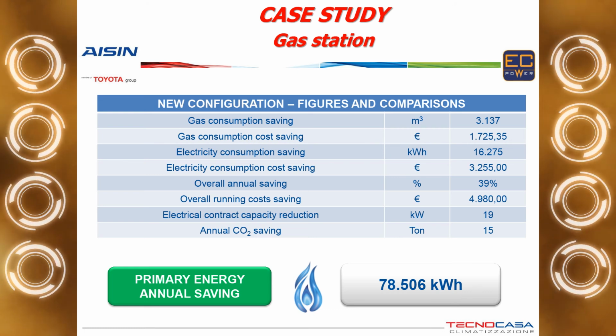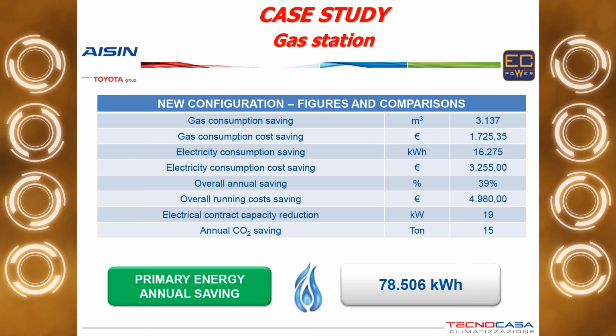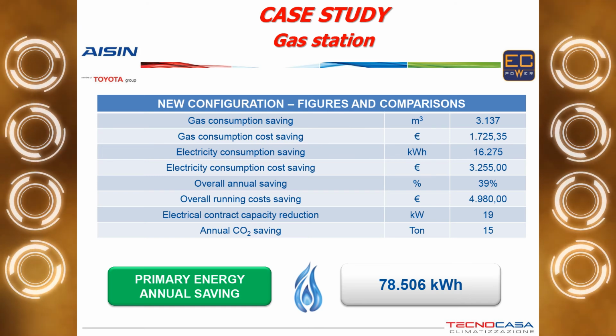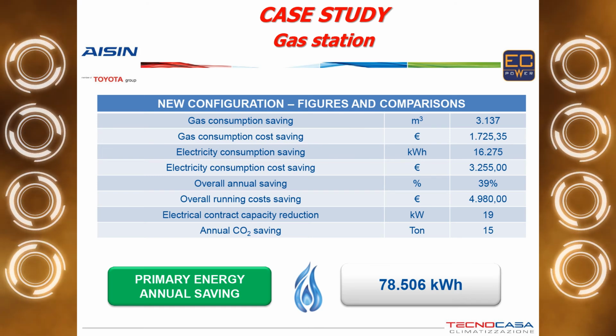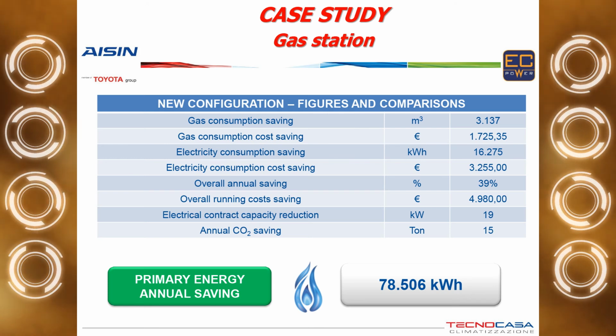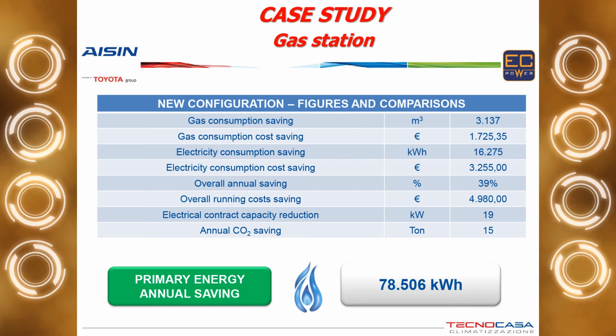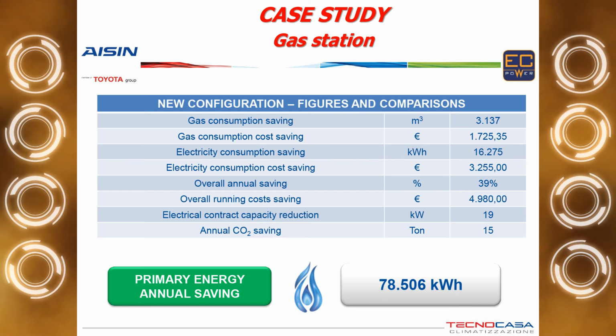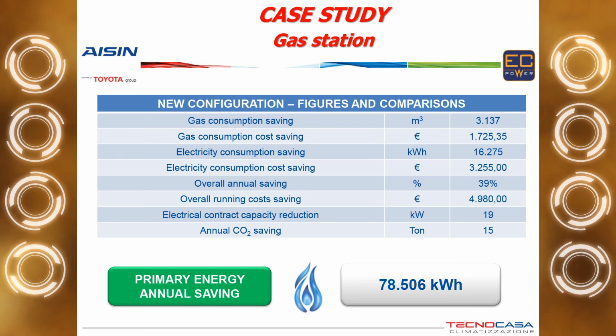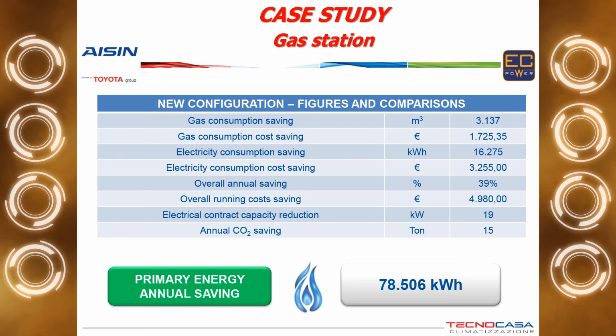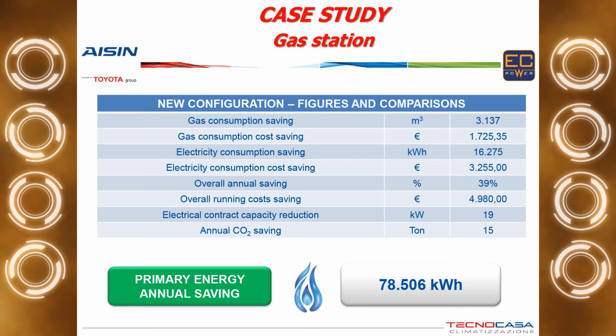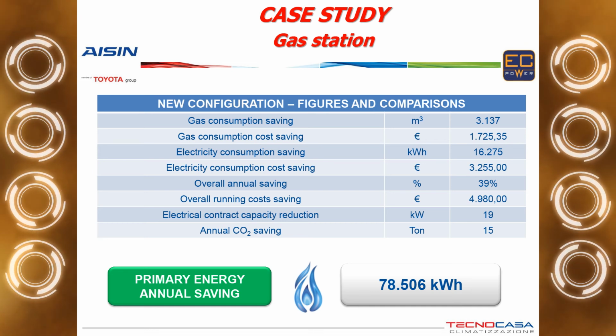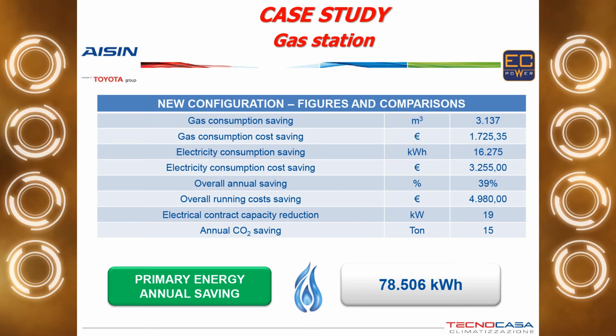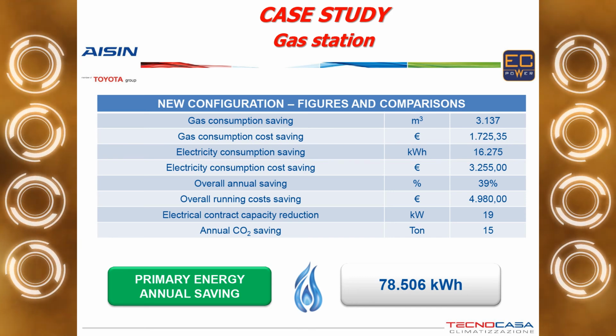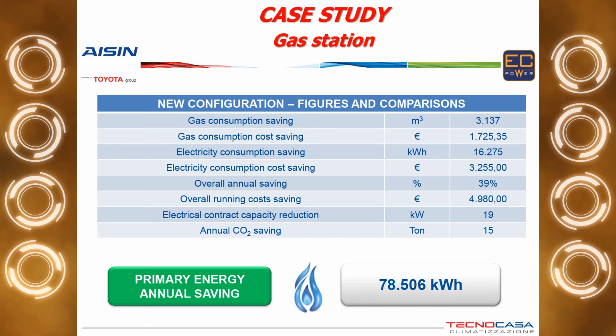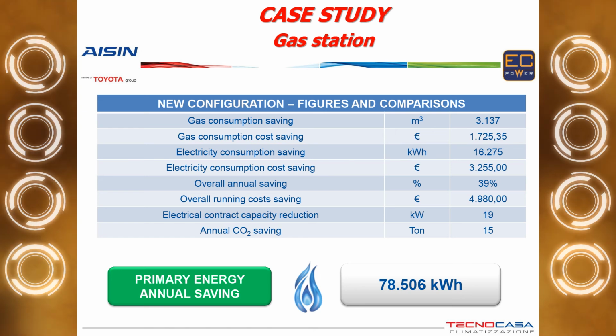And also, we had the possibility of reducing the electrical contract of the gas station for the heat pump quota, for the water chiller quota, 19 kilowatts of capacity, and an annual saving of CO2, which is comparable with 15 tons. If we go back to the primary energy annual saving, what we were able to save in 1 year with the operation of the gas-driven heat pump is about 78,506 kilowatt hours of primary energy.